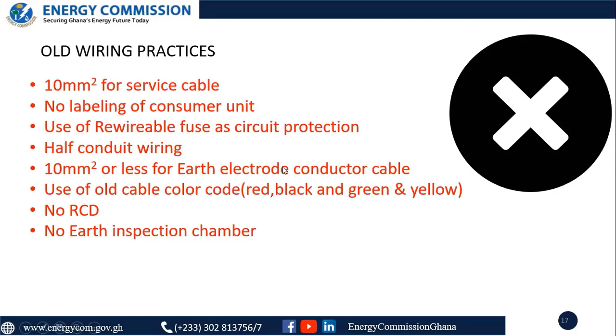The reason being, since we are advocating for 16 millimeter square for your earth cable, if you want current to go readily through a conductor, then there's a relation between the conductor diameter and the resistance. The bigger the conductor size, the lower the resistance. So let's compare 10 millimeter square to 16 millimeter square. A 10 millimeter will have a very high resistance as compared to 16 millimeter square.